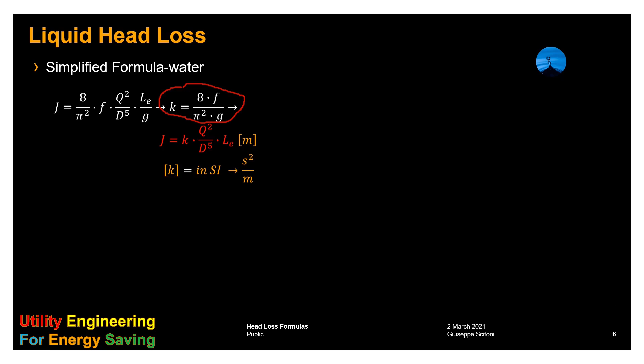And if we stay with steel pipes, then E is known, 0.046 millimeters, and K is only a function of pipe diameter, and we can adapt the empiric formula below, while the units are liter per second for the flow, millimeter for diameter, meters for the length, and J is therefore in meters.